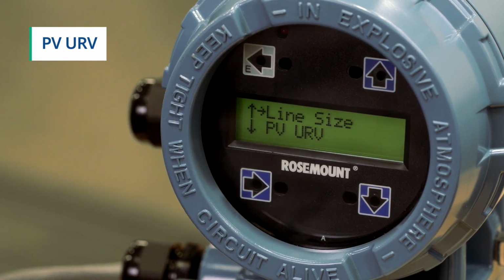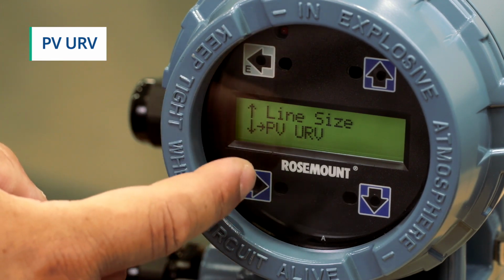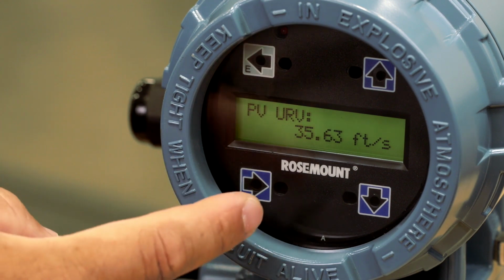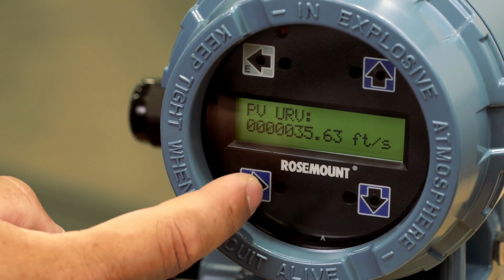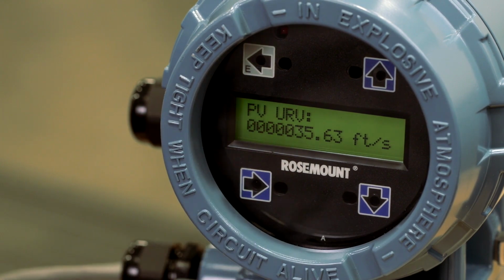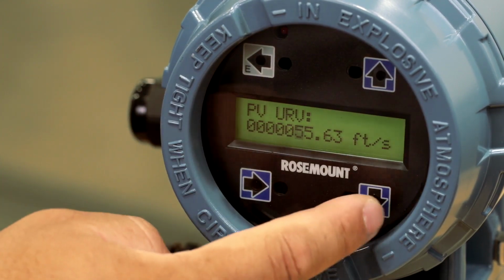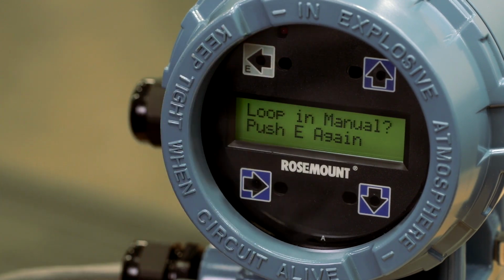To configure the analog output range, first set the primary variable upper range value, or PV-URV. Start by pressing the E button to navigate back to the basic setup screen. Then press the down arrow to scroll through the menu options, and press the right arrow to select PV-URV. Then press the right arrow to move the cursor to the place value that needs to be changed, and press the up and down arrows to increase or decrease the value. When the PV-URV value is entered properly, press the E button to select the value. Finally, press the E button again to save your selection.